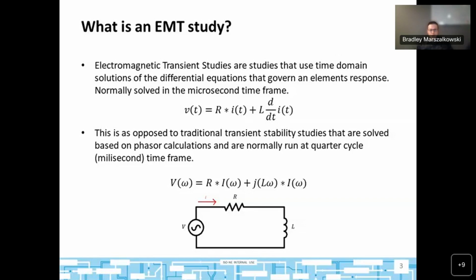Now, this is different from traditional phasor-based calculations in transient stability programs, which are based on positive sequence models. Positive sequence models are abstractions of the full three-phase system. Traditional positive sequence simulation programs assume a balanced system, so they ignore negative or zero sequence contributions for unbalanced phenomena. They'll also normally assume a fundamental frequency and ignore the effects of frequency on frequency-dependent elements. This is partly why they solve normally around a quarter of a cycle, because they're not really meant to model faster phenomena.